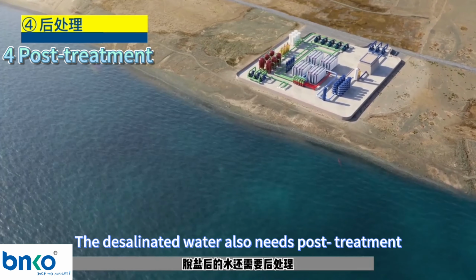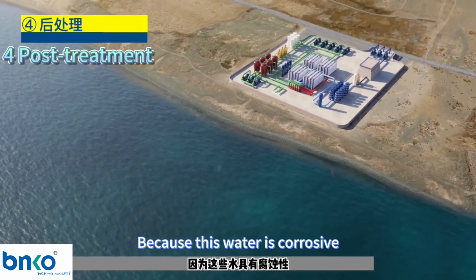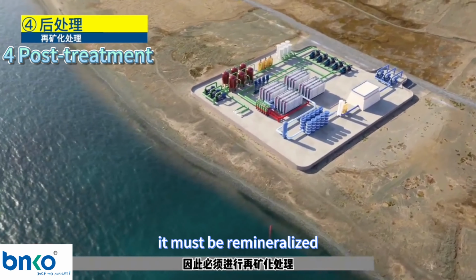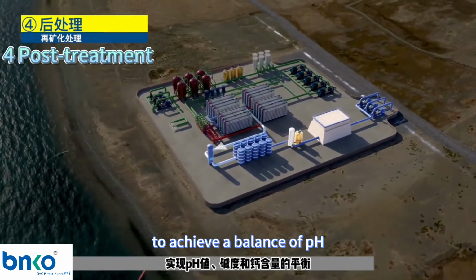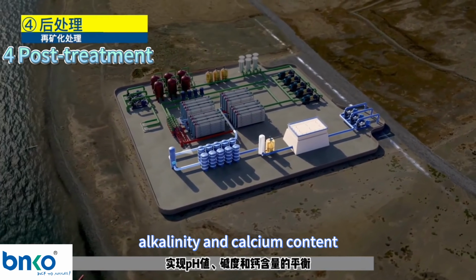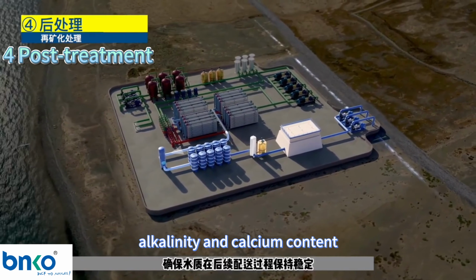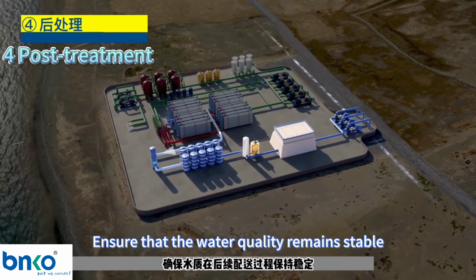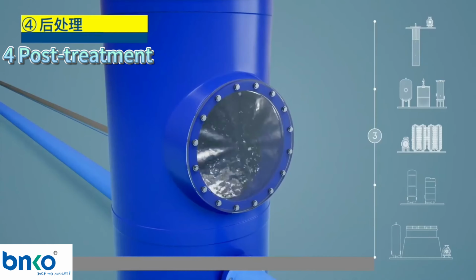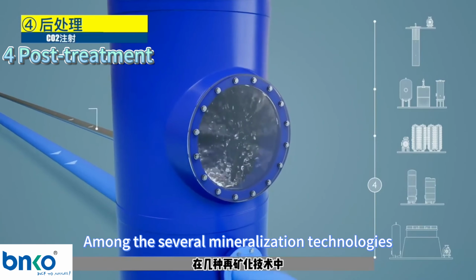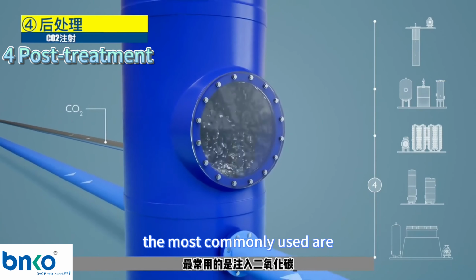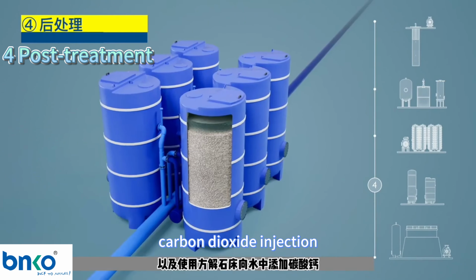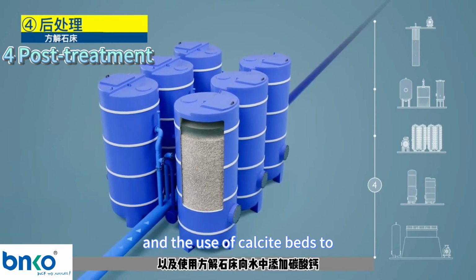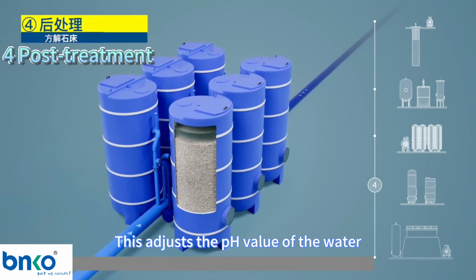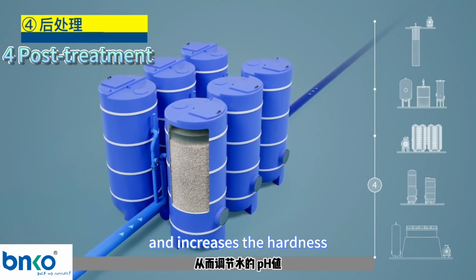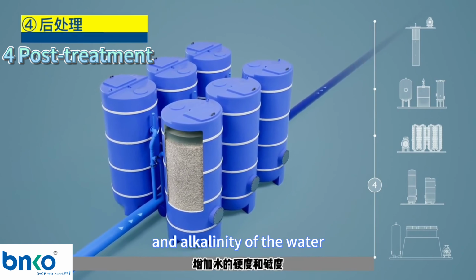The desalinated water also needs post-treatment because this water is corrosive. It must be remineralized to achieve a balance of pH, alkalinity, and calcium content. This ensures that the water quality remains stable during the subsequent distribution process. Among the several mineralization technologies, the most commonly used are carbon dioxide injection and the use of calcite beds to add calcium carbonate to the water. This adjusts the pH value of the water and increases the hardness and alkalinity of the water.